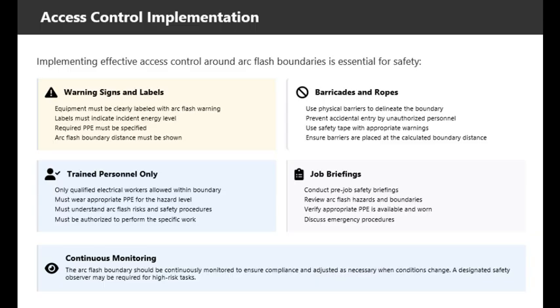Access control means that only trained personnel should be allowed within the arc flash boundary. These workers must wear appropriate PPE for the hazard level, understand arc flash risks and safety procedures, and be authorized to perform the specific work being conducted. Job briefings are essential before any work begins within an arc flash boundary. These briefings should cover the specific arc flash hazards present, review the boundaries and required PPE, verify that appropriate PPE is available and being worn correctly, and discuss emergency procedures in case an incident occurs.